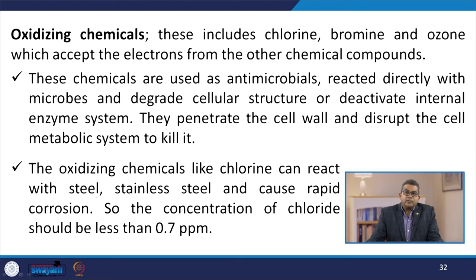Another method is chemical treatment to control microbiological fouling. There are two kinds of antimicrobial chemicals or biocides used in cooling tower water treatment: oxidizing and non-oxidizing. Oxidizing chemicals include chlorine, bromine, and ozone, which accept electrons from other chemical compounds. These chemicals react directly with microbes and degrade cellular structure or deactivate internal enzyme systems, penetrating the cell wall and disrupting the cell metabolic system to kill it. Oxidizing chemicals like chlorine can react with stainless steel and cause rapid corrosion, so the chloride concentration should be less than 0.7 ppm.